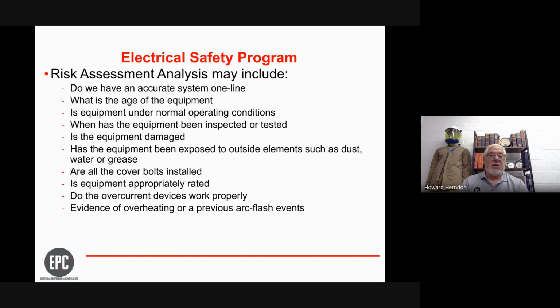Some other considerations are: what's the age of the equipment? Is it under normal operating conditions? Has it been properly maintained to the point that it's not in distress? Has it been tested or inspected recently? Is the equipment damaged? Has it been exposed to outside elements such as dust, grease, water, and other things?